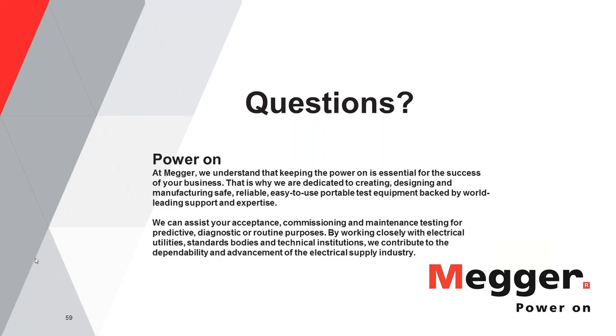Okay. Next question. Could you please go over the short time pickup? Not sure where you get the STPU value. Also, if the short time is set to zero, is it the same as the instantaneous? So trip units have a long time pickup, a short time pickup, and an instantaneous pickup. The short time pickup can be set with various options. It can be selected as a multiple of the long time pickup or of the rating of the current plug. So you can select any of the settings provided on the trip unit. You don't have to stick to a particular value.